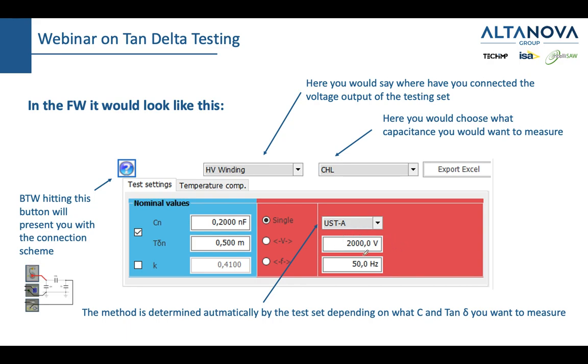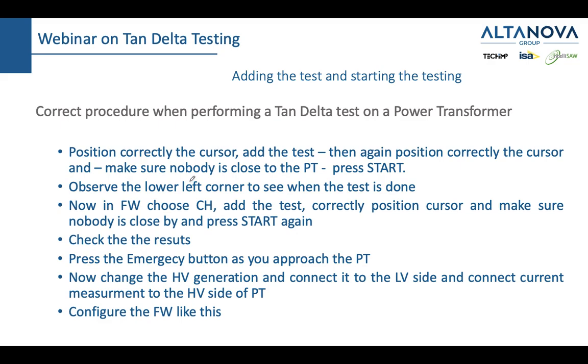You choose the voltage, which is the maximum voltage which you can choose for your transformer, or 12 kilovolts, or 10 is also often used, then the frequency, and then you also choose a single test. This would be a voltage sweep, and this would be a frequency sweep. Here you would see your nominal values, and here you can also do a temperature compensation. Now, after doing that, you would position correctly the cursor, add the test, and make sure that nobody is close to the power transformer. Dear friends, safety is of the utmost importance when doing this test, because 10 kilovolts or 12 kilovolts or even 1 kilovolt is more than enough to hurt a human being. So be mindful when executing this test.